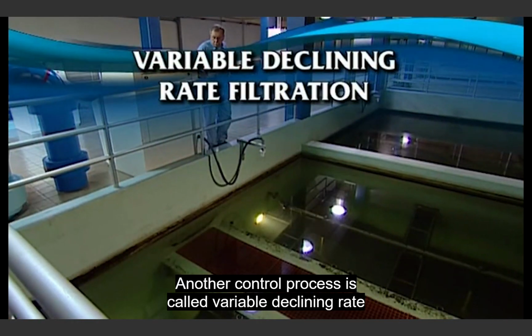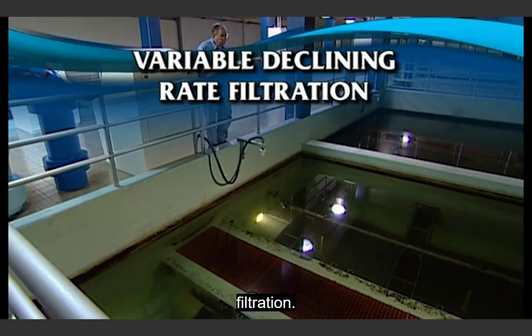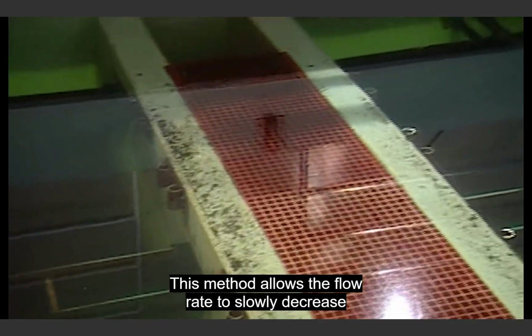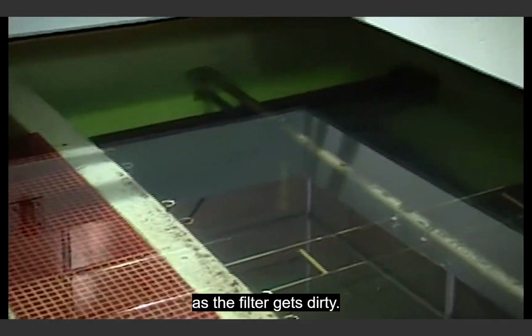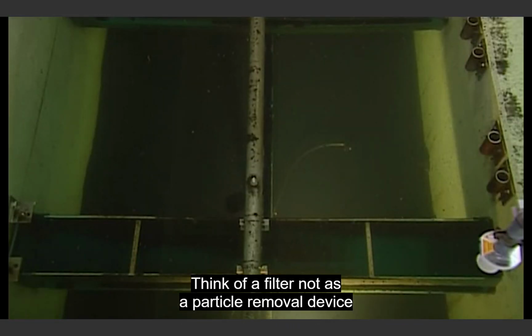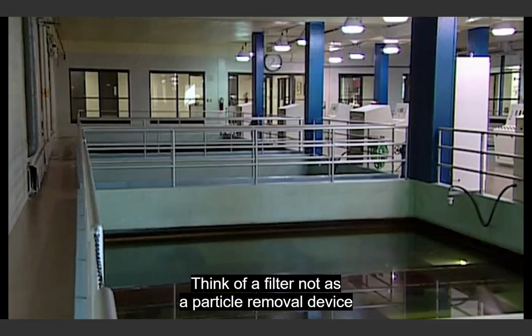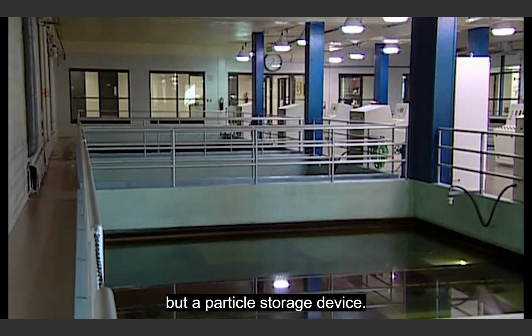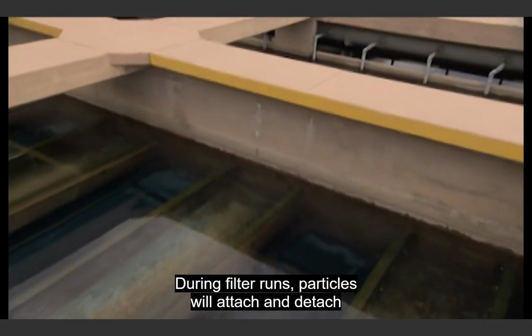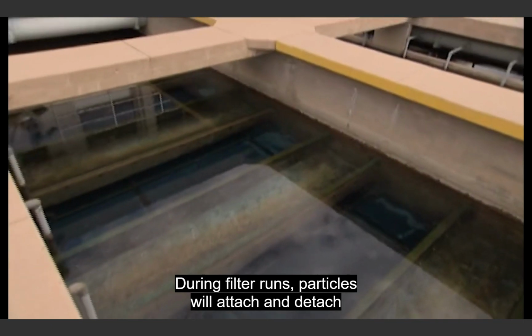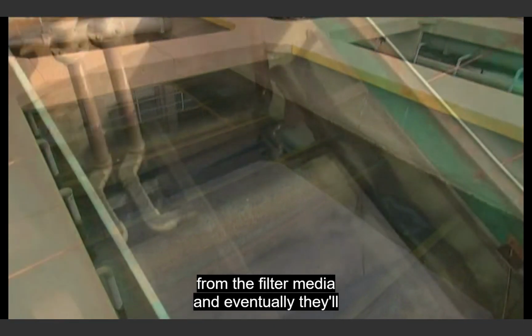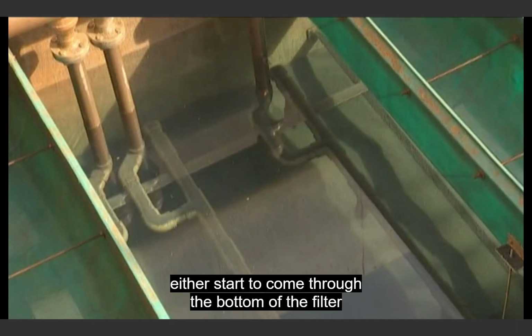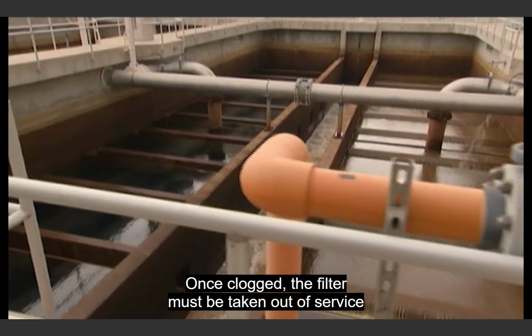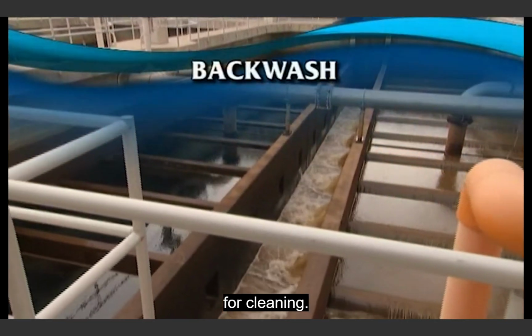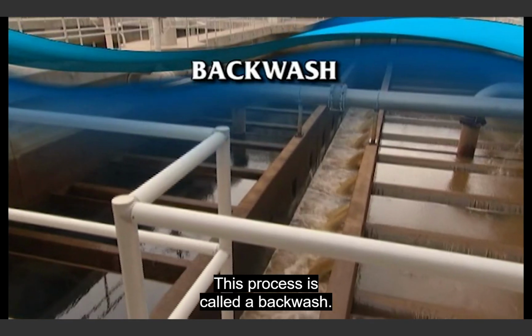Another control process is called variable declining rate filtration. This method allows the flow rate to slowly decrease as the filter gets dirty. Think of a filter not as a particle removal device, but a particle storage device. During filter runs, particles will attach and detach from the filter media, and eventually they'll either start to come through the bottom of the filter or the filter will get clogged. Once clogged, the filter must be taken out of service for cleaning. This process is called a backwash.